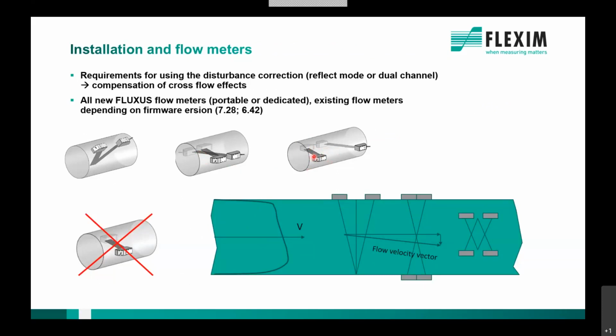Some of you might know, others might not, we have something called cross-flow effects. Cross-flow effects are basically a flow velocity vector which is not parallel to the pipe, it's off of it, and cross-flows can never be predicted. They depend on the pipe, on the disturbance, and always also on the flow velocity, so they may vary. That's why it cannot really be corrected. That needs to be compensated by a recommended installation, which in the easiest way is a reflect mode installation.